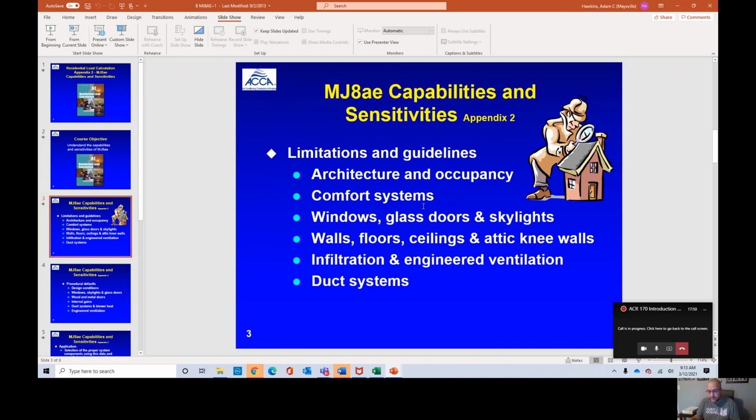Or you go into a commercial setting. So even if it may be a home, but that home has been used for commercial purposes and has a lot of people in it, then you may have to either calculate those people or use Manual N. So like a church, for example, a church may be 1,500 square feet, but small church. But if it has 50 people in it, that's going to calculate a lot differently than a 1,500 square foot house.